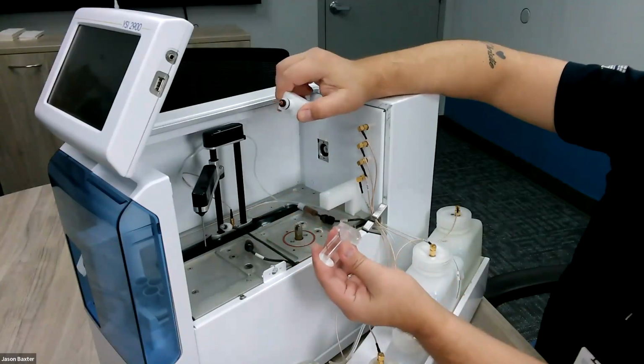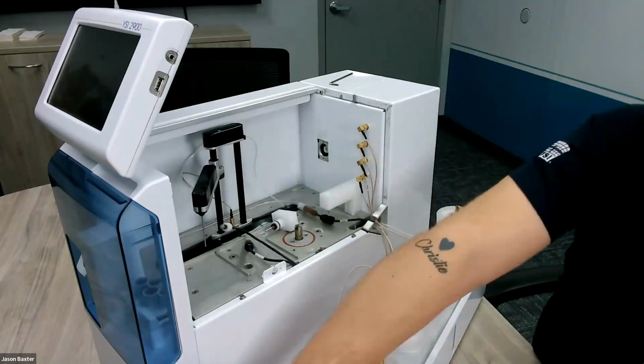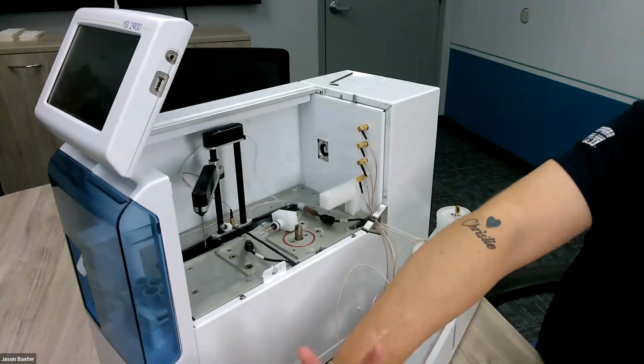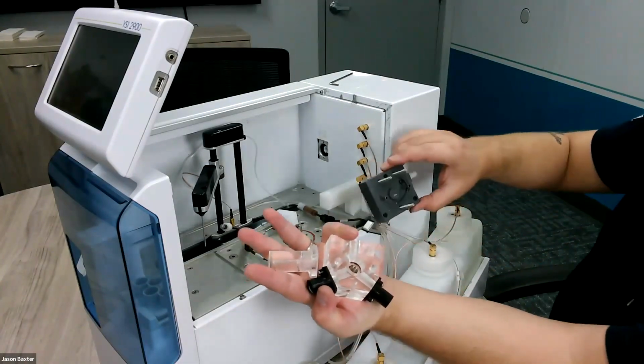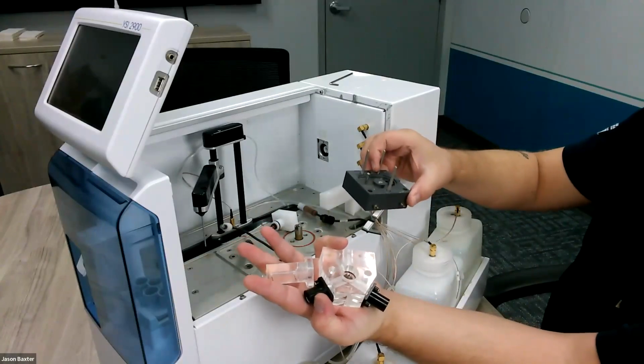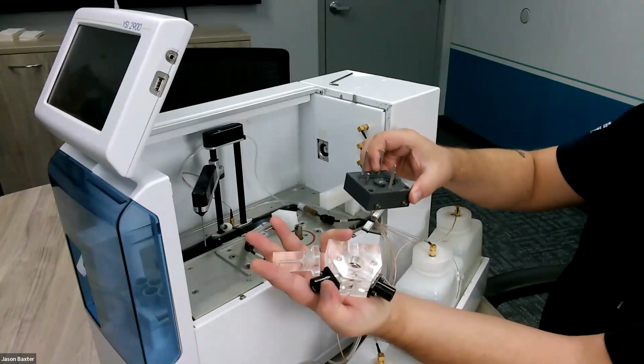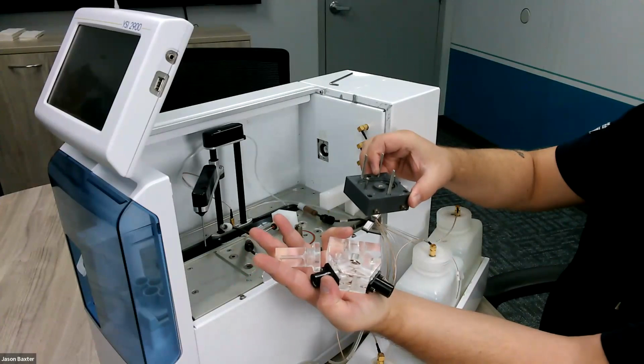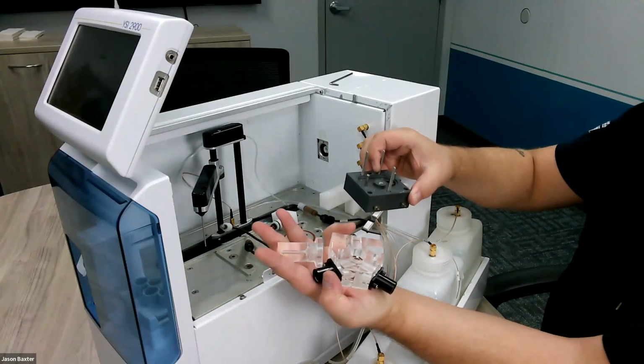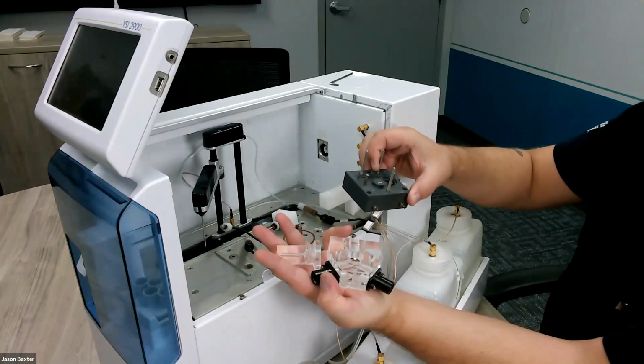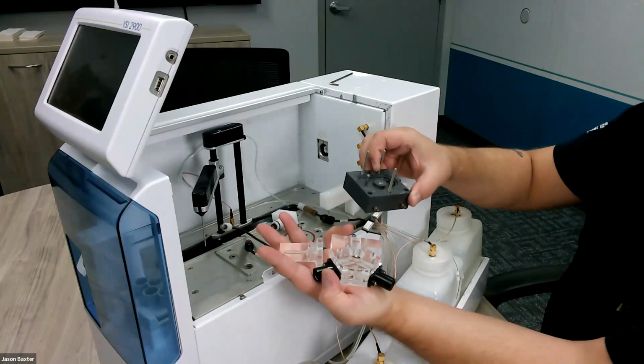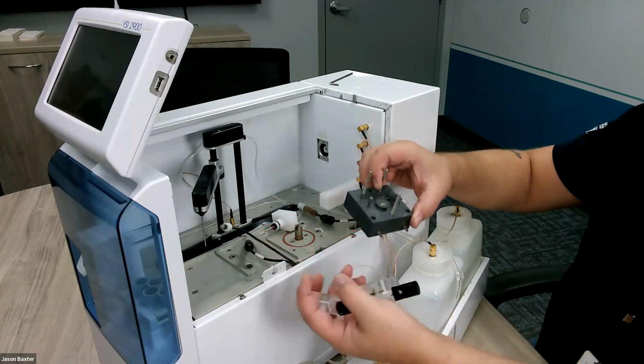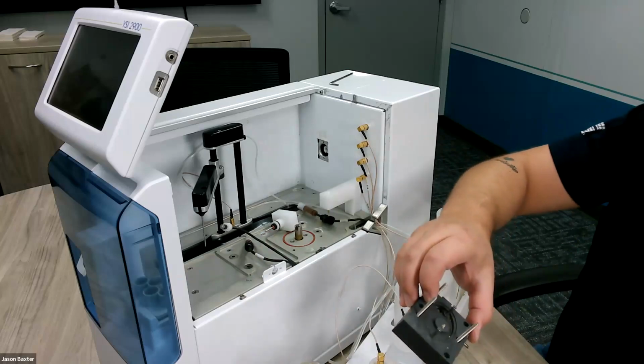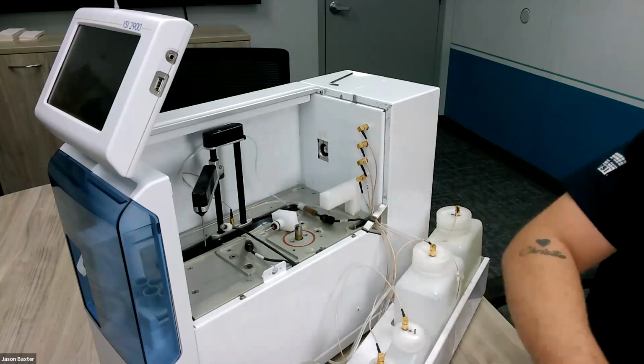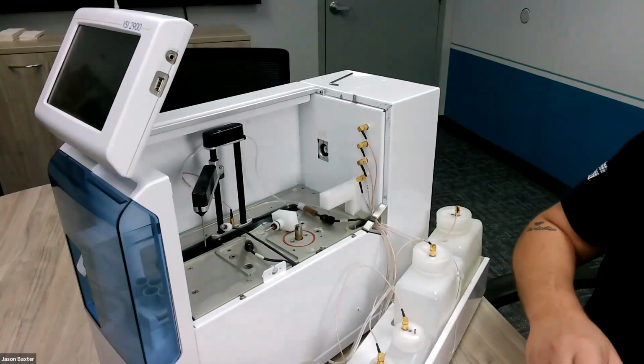Take your sipper pump body, set it down momentarily. You're going to want to take your waste chamber, your sipper pump housing, and your sample chamber. Put these into a container that has 10:1 hypochlorite or bleach solution, and let them soak for at least 15 minutes. Anywhere from 15 to 30 minutes is just fine. So we're going to set these off into our bucket so they can soak, so they will get themselves cleaned up.